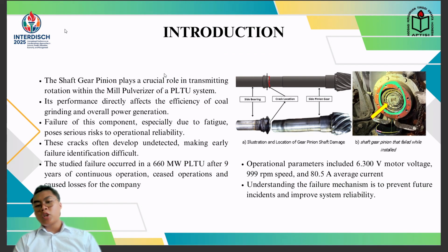which caused operational loss for the company. Operation parameters include a 6,300 volt motor voltage, 999 RPM speed, and 80.5 ampere average current. Understanding the failure mechanism is needed to prevent future incidents and improve system reliability.